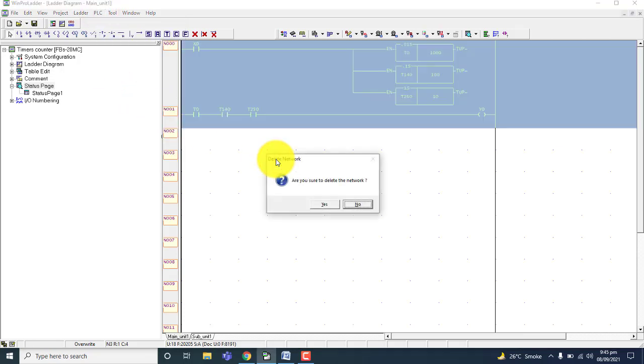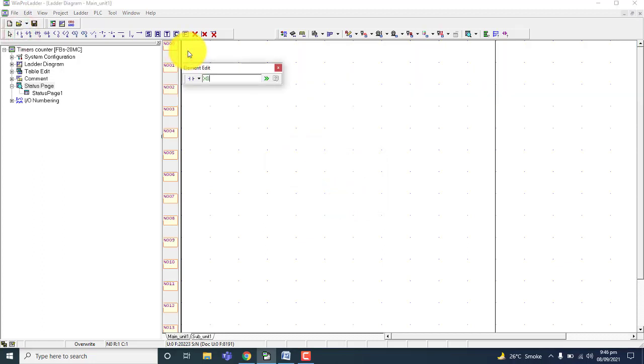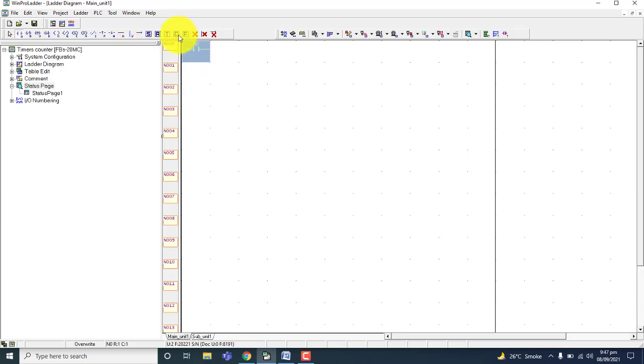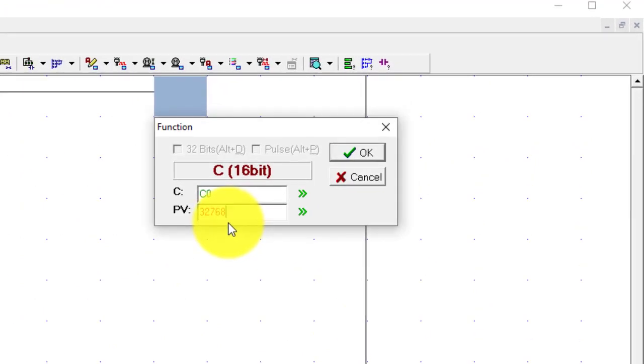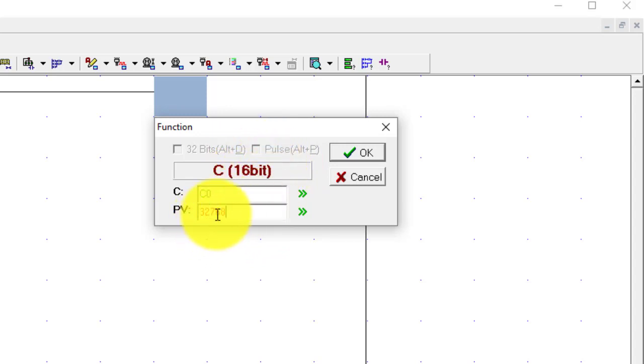Now we will use the counter. Put input X0. I will use a 16-bit counter and a 32-bit counter — one is the non-retentive counter. First one is C0, which is the 16-bit retentive counter. Its value will not be lost if PLC power is lost. If I put the value 32,767 it is acceptable for the 16-bit counter. But if I increase the value beyond that, it will go red — meaning this is not an acceptable value for the 16-bit counter. Its maximum value is 32,767.